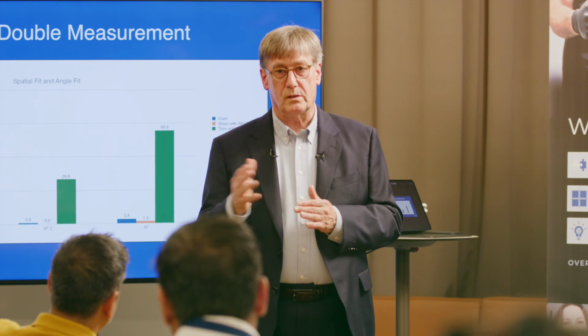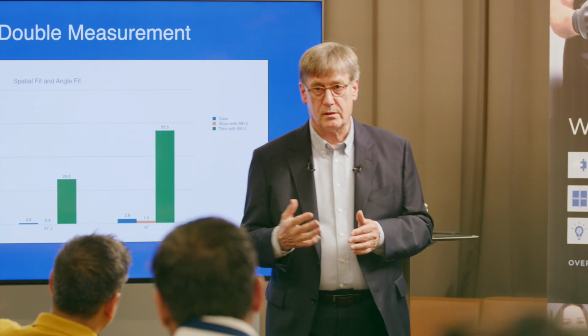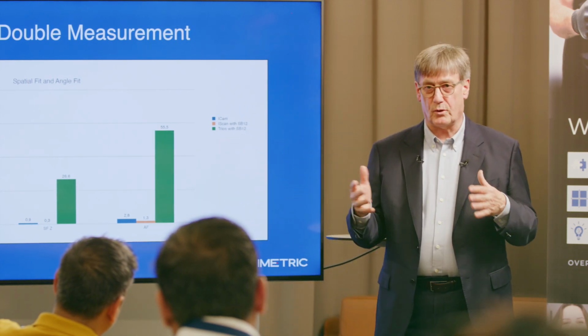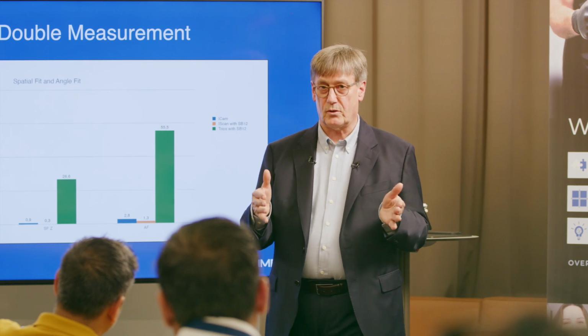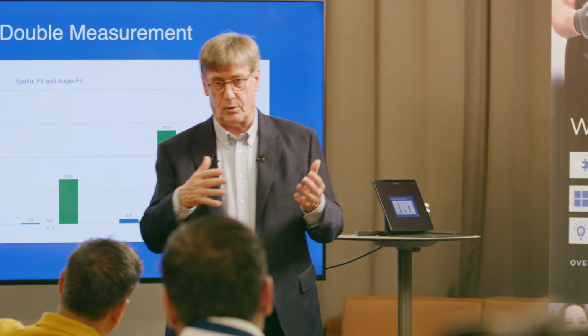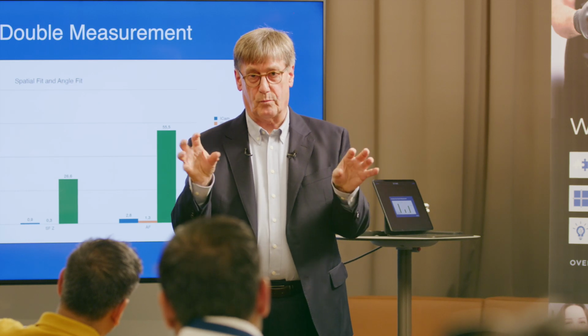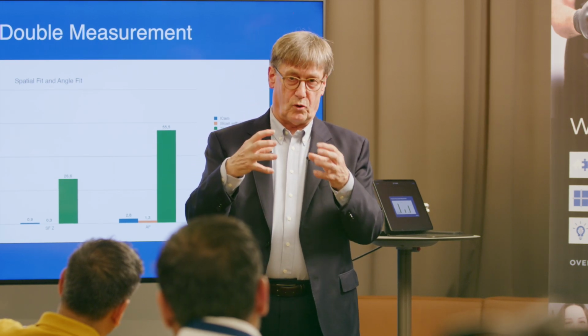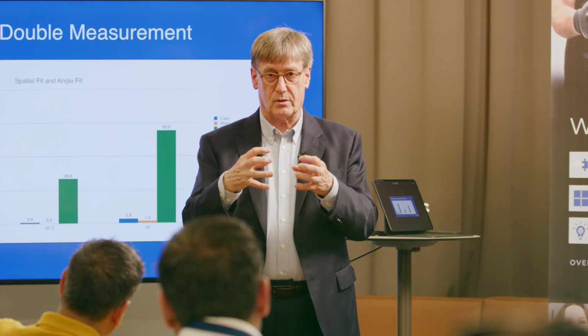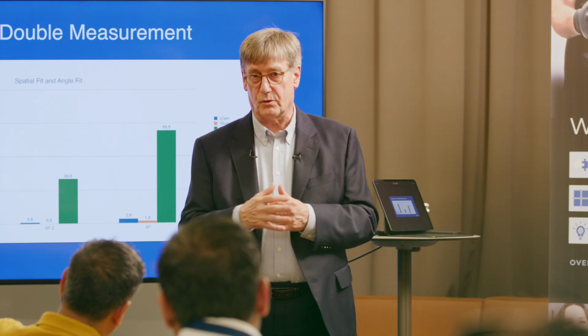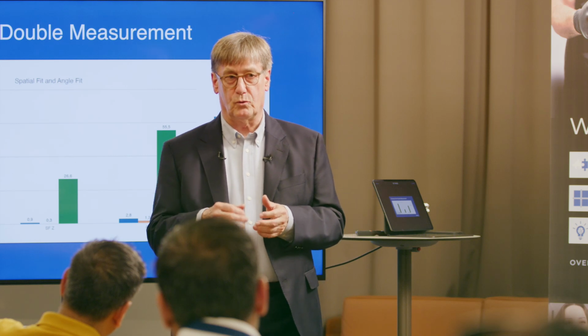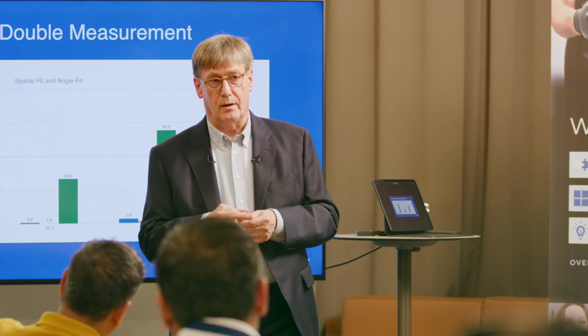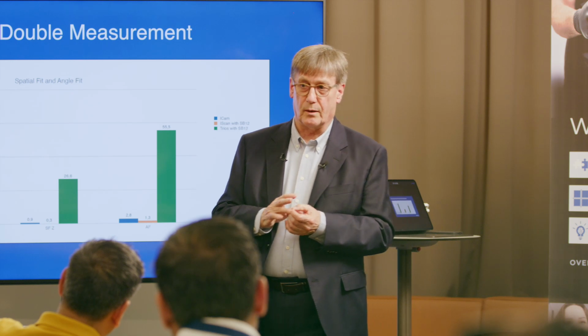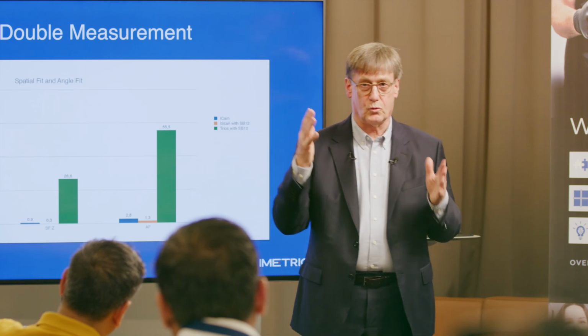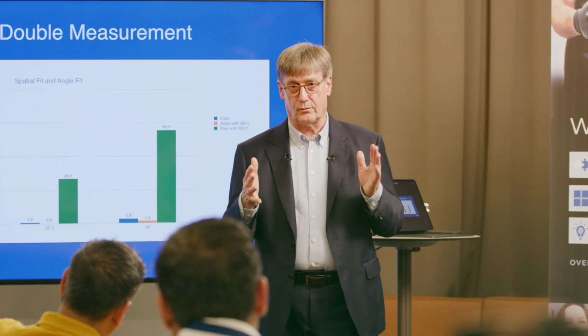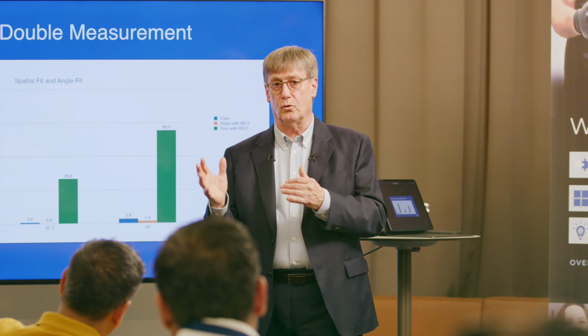What we see is we have done some upgrades. The machine after 3 years starts to get a little bit out of calibration. That's logical, because the calibration that you do only calibrates the relationship of the cameras. It doesn't calibrate the internal geometry between lenses and the cameras. And with enough banging, everything gives over time. The other thing that we see, people do destroy calibration plates. And that's something that we're thinking about how we do this, because probably we should recalibrate and recheck everything after 2 years. But that's also something you can do on your own.